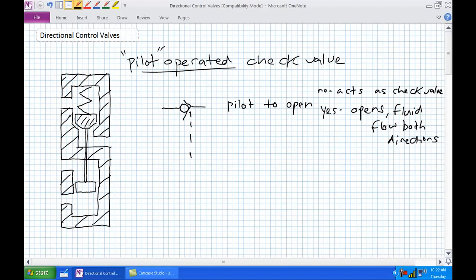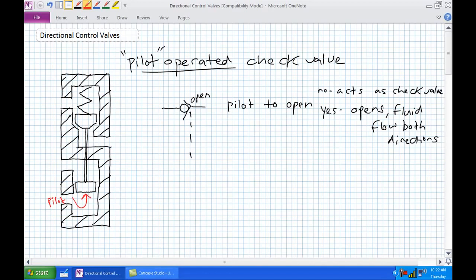How do you know it's a pilot-to-open check valve? The pilot signal is going to the open side — it's pushing the ball back to open the valve. In our cutaway, a pilot-to-open has its pilot pressure coming in and pushing on the piston side. With no pilot pressure, it allows flow in one direction and blocks it in the other — just like a regular check valve.